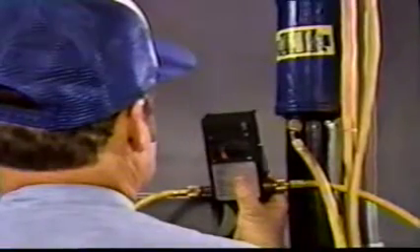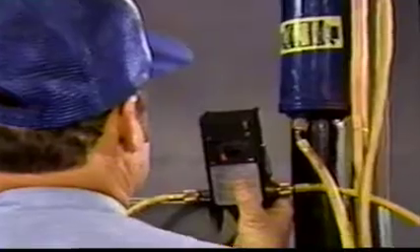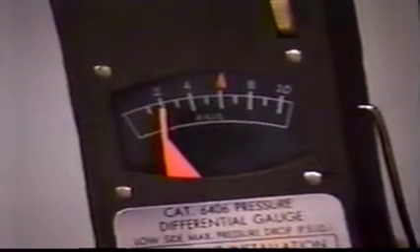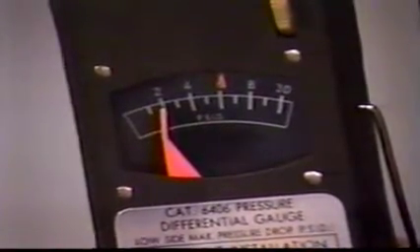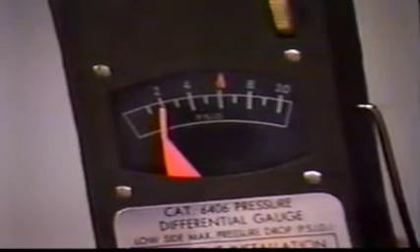It should start with the installation of a special burnout filter dryer in the liquid line. A suction line filter dryer should also be installed in the suction line. Both of these filter dryers should be oversized. It's the suction line filter dryer that will be the determining factor in changing the liquid line filter dryer following a burn. The suction line dryer is changed out until the pressure drop is below acceptable limits. Whenever the suction line dryer is changed, the liquid line dryer should also be changed.